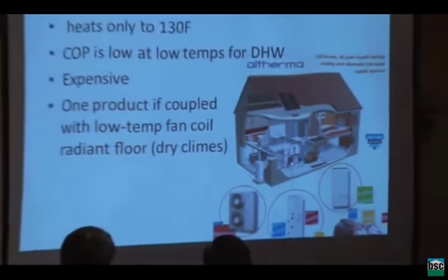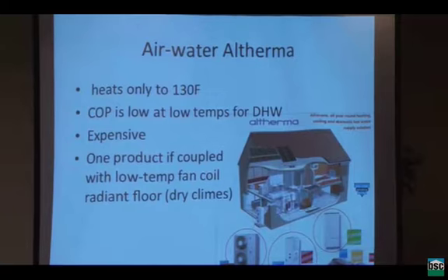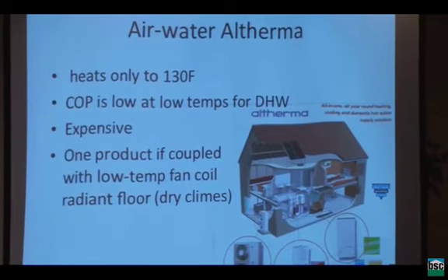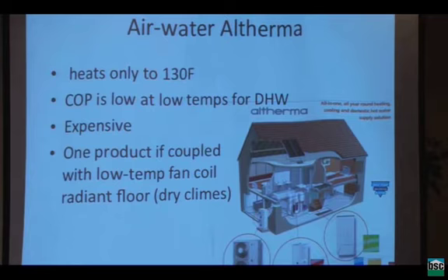Why does it only heat to 130 degrees? Because it uses, if you'll notice on the brochure there, R410. And that's about as far as you're ever going to go with R410. You have to change to a different refrigerant to get hotter water, because the refrigerant will simply break down at higher pressures and temperatures. It's the curve of the enthalpy curve. So at outdoor temperatures of like 20 degrees, if you try and produce 130-degree water, your COP sucks. It's like 1.5, 1.6. And they're not very forthcoming about providing these full charts of data, so I'm piecing together various published tests.